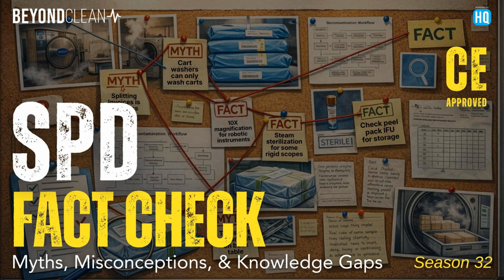Of course, there are going to be variables by manufacturer. If talking just about rigid endoscopes, there's a specific subset of bonding agents that most manufacturers will use for a variety of reasons. One is we know that they withstand certain parameters in certain devices. We also know, and Jamie mentioned this in our earlier conversation that wasn't recorded, something about cleaning validations and studies. So it makes sense as a manufacturer to piggyback off other test methods that have proven this bonding agent works as far as sterilization efficacy and product durability. So we might choose bonding agents from that perspective.